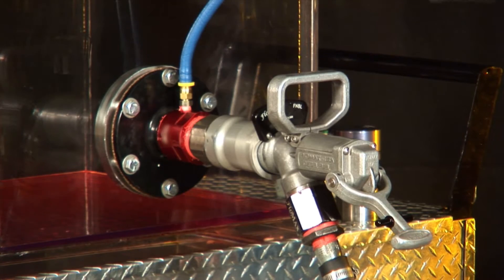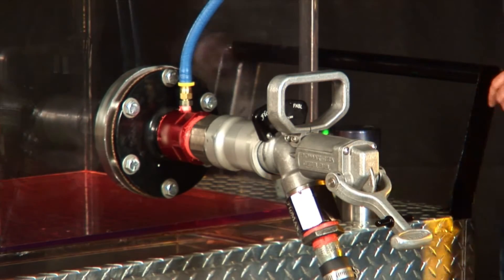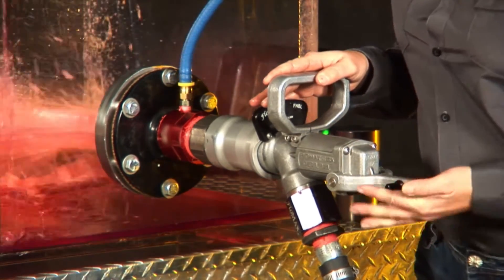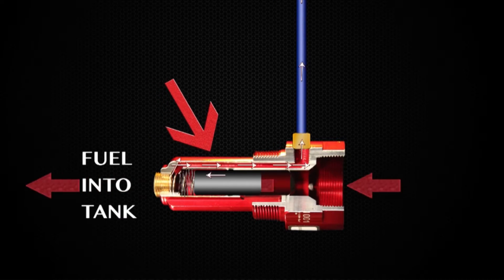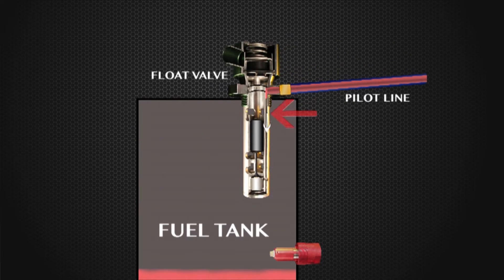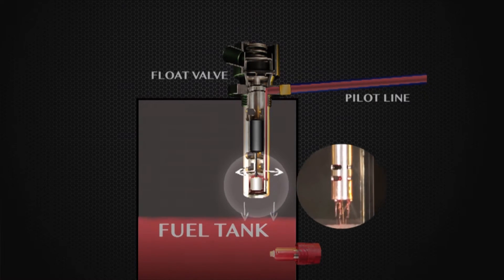The way this system works is when I hook up my fuel nozzle, fuel pressure opens our fuel inlet valve and fuel goes into the tank. As the tank is taking fuel, a small portion of that fuel is being redirected through the valve, then travels up the pilot line, and down the passageway in the float control valve, and overfills the bottom chamber in that float control valve.